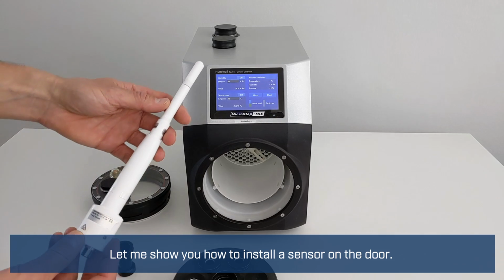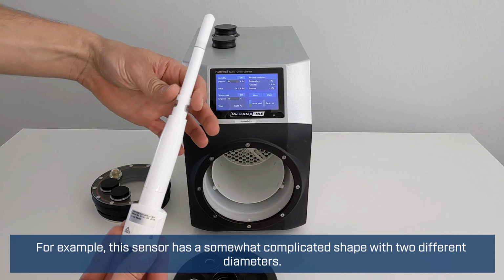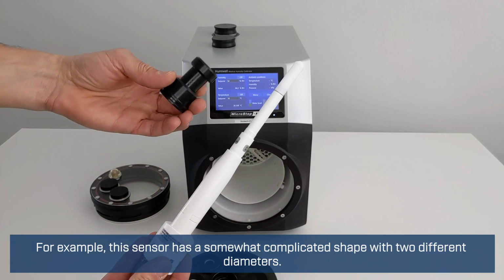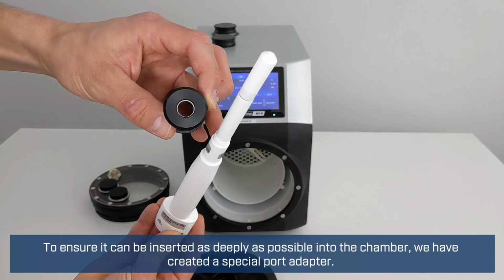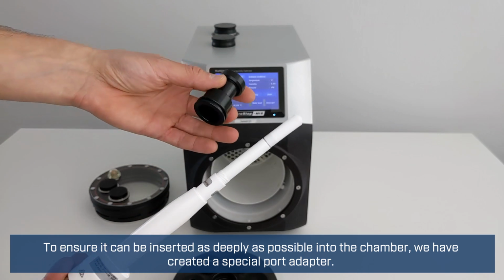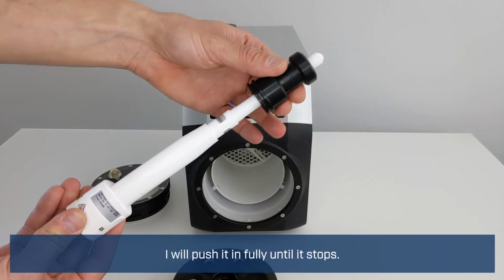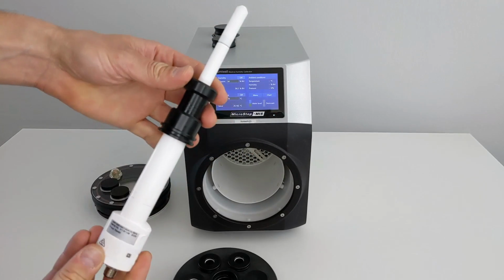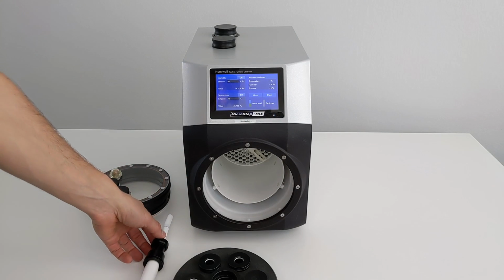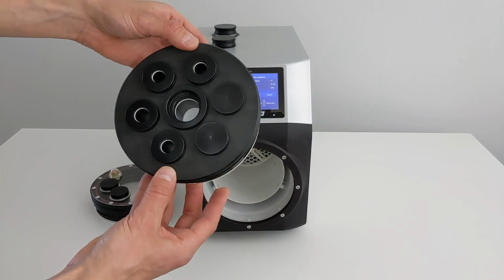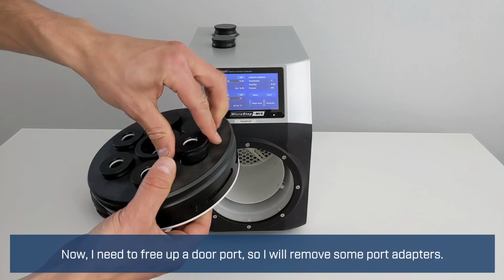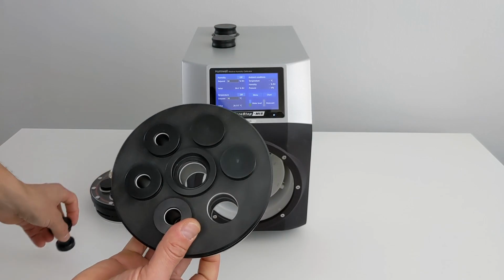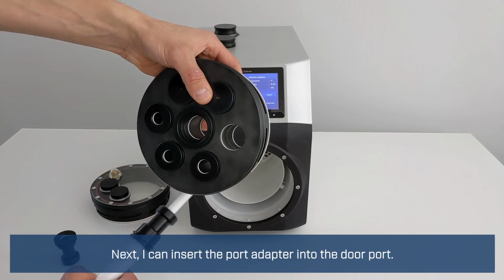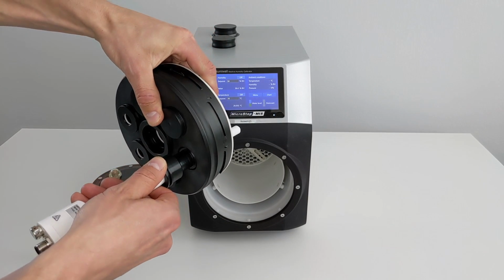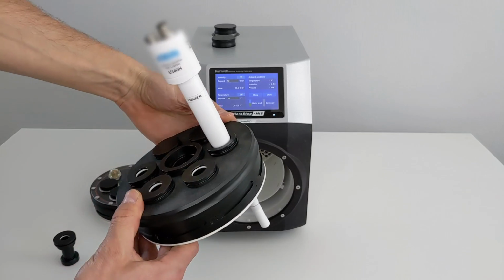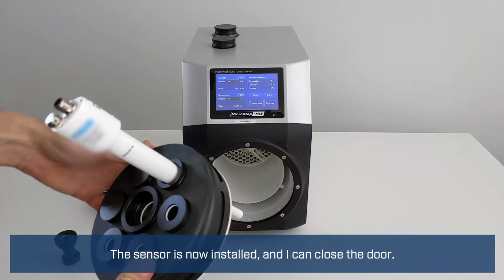Let me show you how to install a sensor on the door. For example, this sensor has a somewhat complicated shape with 2 different diameters. To ensure it can be inserted as deeply as possible into the chamber, we've created a special port adapter. I'll push it in fully until it stops. Now I need to free up a door port, so I'll remove some port adapters. Next, I can insert the port adapter into the door port. The sensor is now installed and I can close the door.